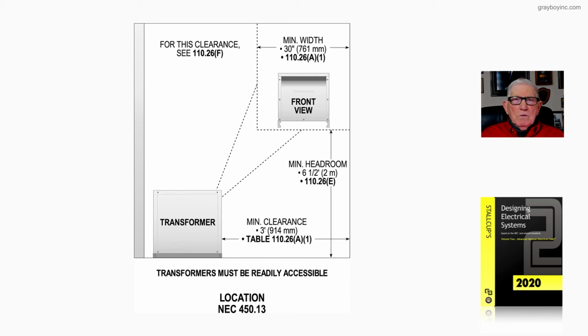Now notice that 450.9 of the NEC will not allow you to put things on top of the transformer or store things there. Electricians, a lot of times in a facility where they have a transformer, will set their lunch kit on it and other things to keep it as warm as possible. Sometimes, if a transformer is loaded up and it's real cold, we would put our hands up close and let the air that circulates have a little heat from those windings, if the transformer was loaded up with enough current to provide that kind of action.